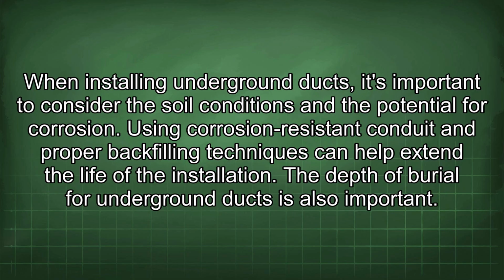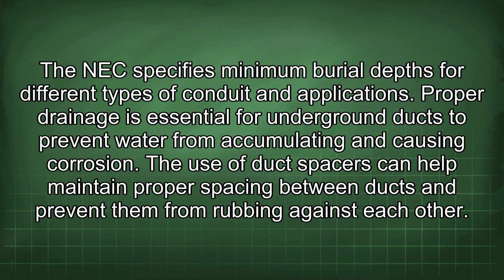When installing underground ducts, it's important to consider the soil conditions and the potential for corrosion. Using corrosion-resistant conduit and proper backfilling techniques can help extend the life of the installation. The depth of burial for underground ducts is also important. The NEC specifies minimum burial depths for different types of conduit and applications. Proper drainage is essential for underground ducts to prevent water from accumulating and causing corrosion.